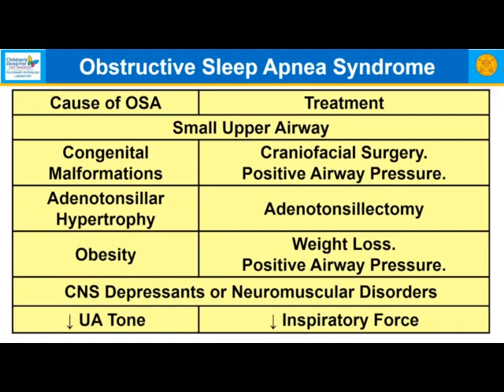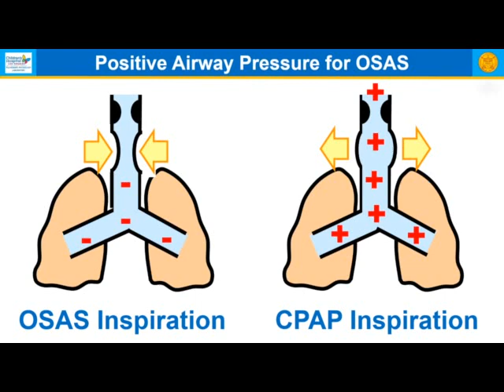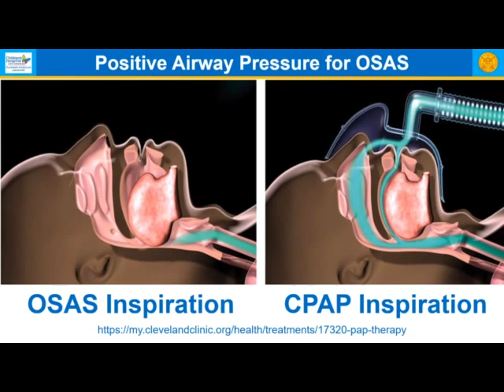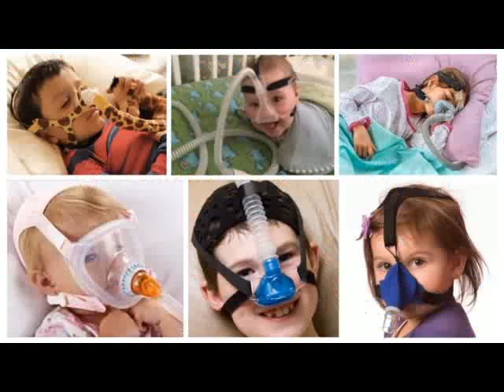So positive pressure for obstructive sleep apnea. Basically in the normal situation, in inspiration, remember you have to generate a large negative intra-airway pressure so that pressure inside the airway is less than outside and you get dynamic compression. If you use CPAP, basically you're going to use a pneumatic splint. You're going to provide positive pressure in the airway, which is going to help to keep the airway open even during inspiration. Shown here, an inspiration with airway obstruction, you can see no flow, and then positive airway pressure basically is going to provide pressure here, which keeps the airway open during inspiration.